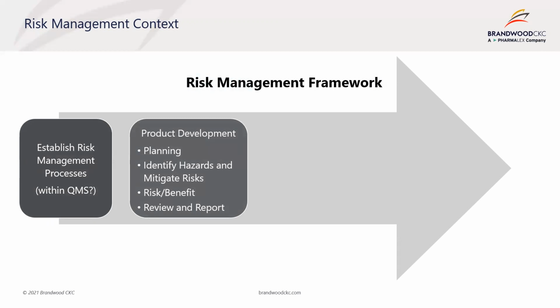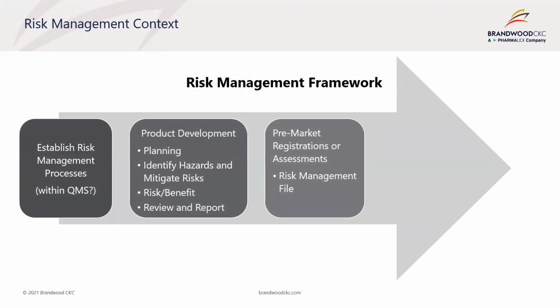During product development, the key activities include risk management planning, identifying hazards, evaluating and mitigating risks, conducting risk-benefit analyses, and finally, review and reporting of the final status. We will cover these in more detail later in the webinar. Once the product is ready for release to market, the pre-market regulatory registrations, 510(k)s and CE marking conformity assessments, can be conducted, which will require that all activities are completed and a risk management file is established. The product can be released and then begins the ongoing monitoring while the product is in the field.